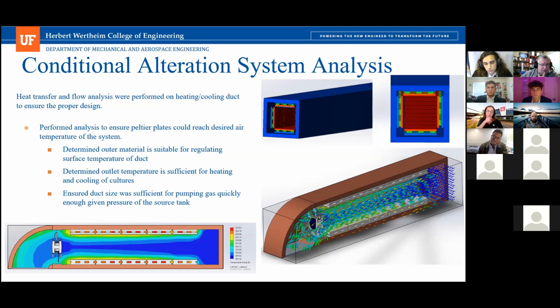While we're here, you said that the fan isn't turning in this simulation, but is it actually in there, or did you just add it later so that we could see? The fan is actually in there, but it's not actually rotating. There is a SolidWorks imaginary fan at the end, using a fan curve that SolidWorks had, so it pretends there's a fan actually rotating there, but not physically in there. It's sucking air out at a rate a fan would, but our actual fan is stationary.